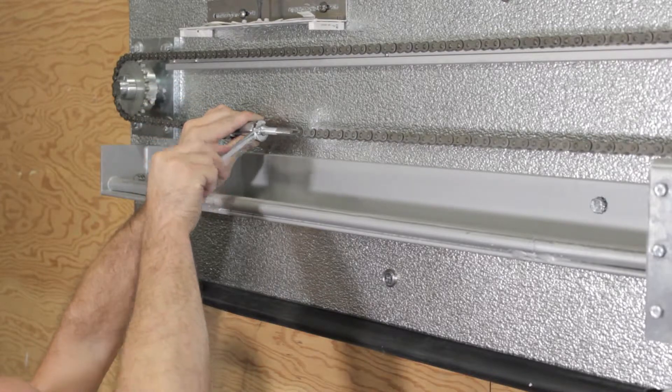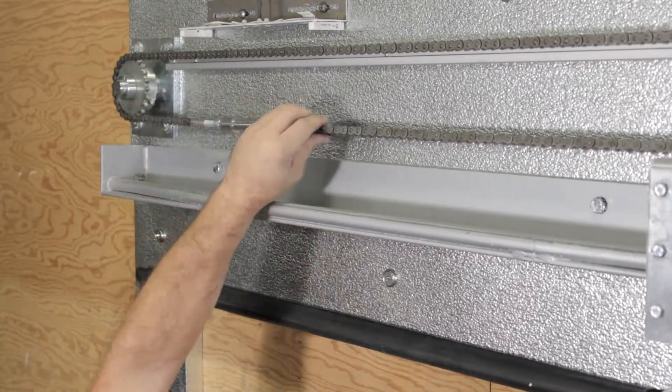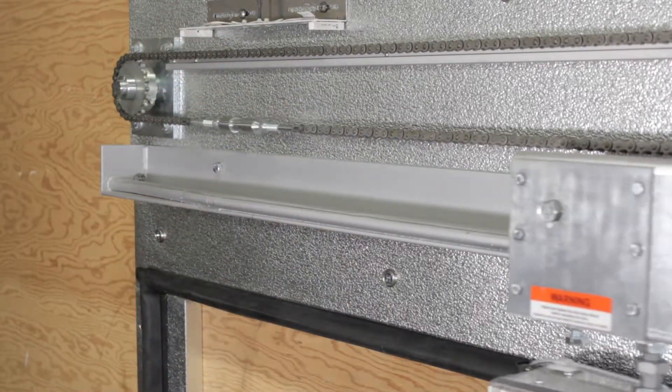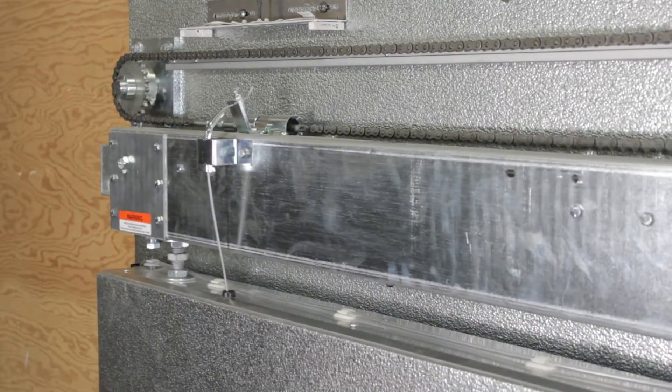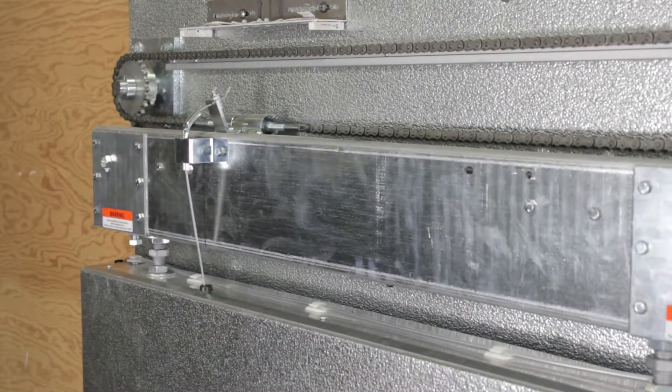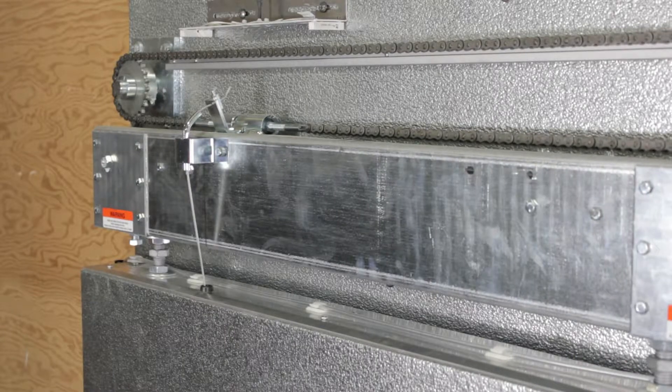To reconnect the door to the chain, move the door sideways until the door catches and free movement stops. The drive chain bullet will automatically engage the release latch when the drive release tube and the bullet align.